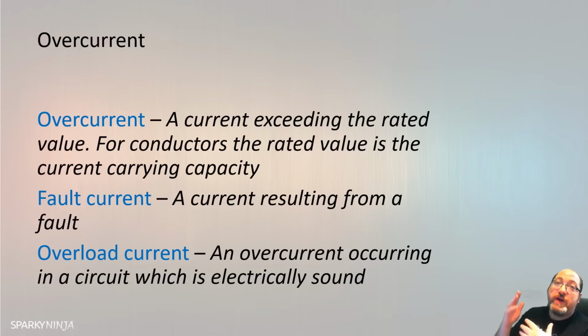Quite often this is a very high fault, because we install our circuits to introduce very low values of impedance, either through a short circuit, line to neutral or line to line for 3-phase, or from any line conductor to earth. We deliberately install a circuit of low impedance to achieve high fault currents. The objective is that high fault currents will then be translated to very quick disconnection times.